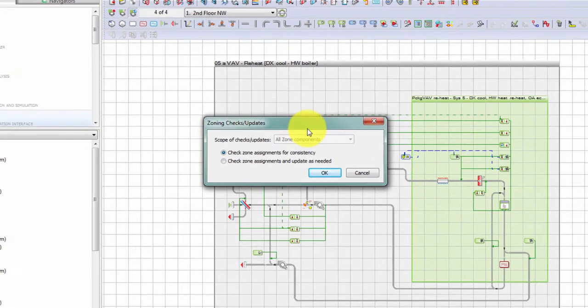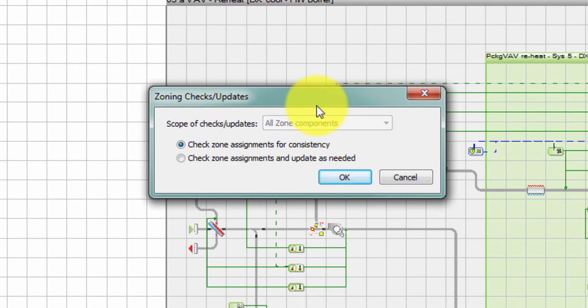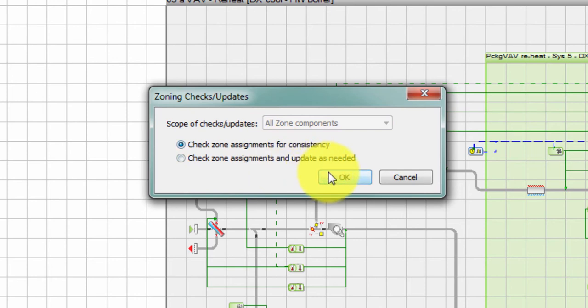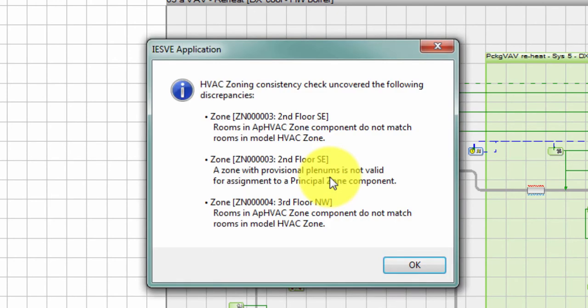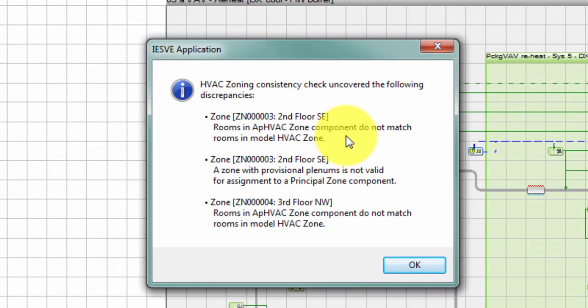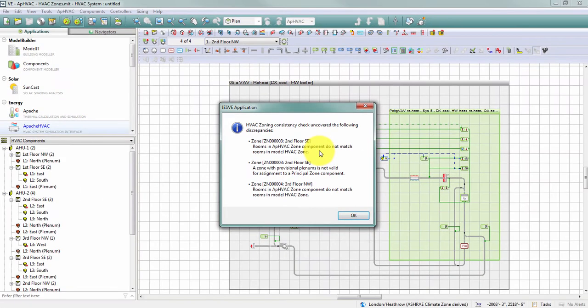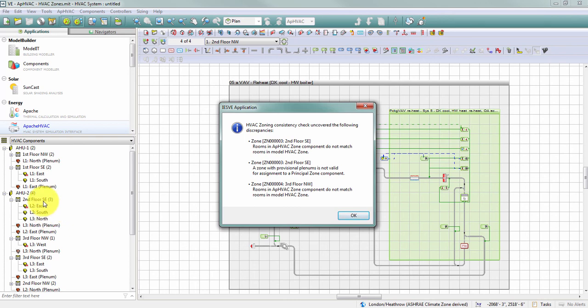I have the option to ask it to just check for consistency or I can have it check for consistency and update as needed. So if I just check for consistency to start, it tells me right away that I've got a few mistakes here that I need to correct in my model. My second floor zone contains a space that it didn't previously have. So this first error message tells me that my Apache HVAC zone component doesn't match the rooms that are in my HVAC zone grouping scheme. The second error message here is noting that I now have two plenums associated with a single zone, which isn't possible. So I need to make some corrections there to my plenums.